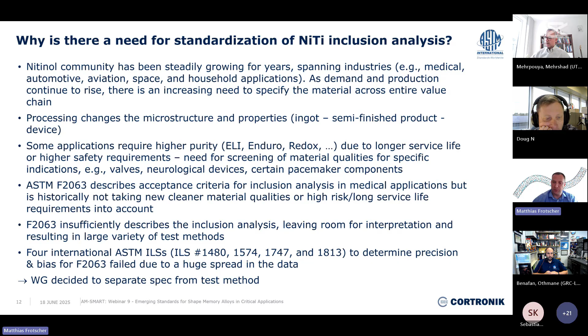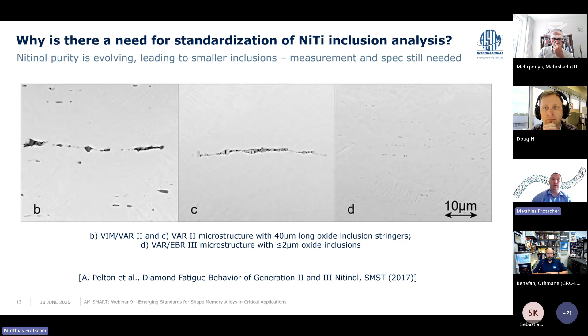These SEM micrographs from Pelton illustrate the evolution of material purity in binary nitinol alloys over the last couple of years. And you can see that optimized melting methods have resulted in higher purity alloys by reducing the carbon and oxygen contents, leading to fewer and smaller inclusions. As mentioned earlier, this does not matter for every application, but it is important for higher risk requirements, where the increased purity can allow for higher fatigue safety factors and a significantly longer service life. However, the need for a suitable and reproducible inclusion test method remains across the whole value chain, from melt ingot to semi-finished product all the way to the devices.